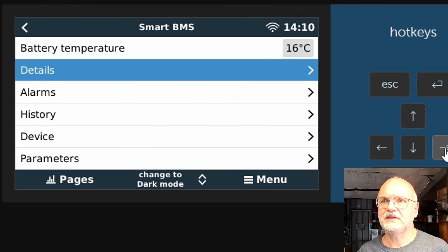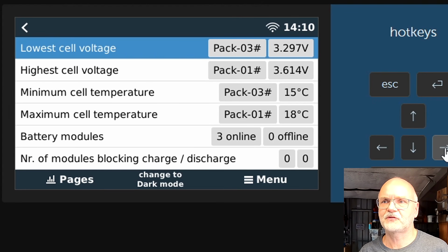And if we have a look in the details of the smart BMS in the Victron console, we should actually see one battery offline. No, it's not. You would expect one of the batteries is now offline because the charge MOSFETs have turned off, but this is not the case, because we still can discharge the battery. It's fully charged, doesn't take any more, but it's still online and we can discharge it.